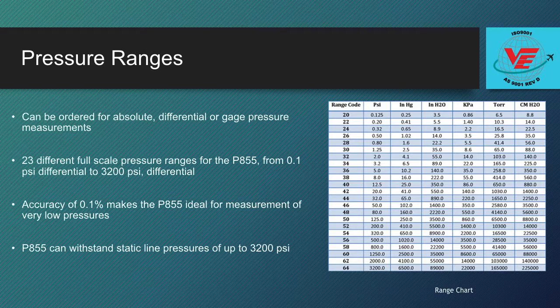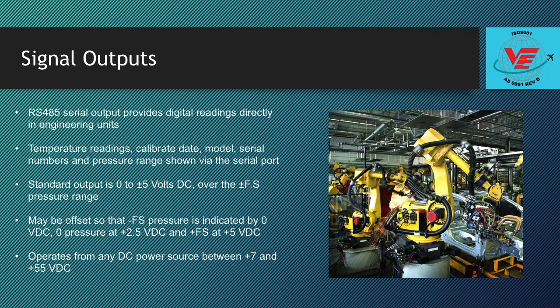An accuracy of 0.1% makes it ideal for measurement of very low pressures. In addition, every P855 can withstand static line pressures of up to 3,200 psi gauge on both ports. This means a low-range P855 can be used to measure small pressure drops in a system even if that system is running at a high line pressure. Zero shift is limited to 1% per kpsi.